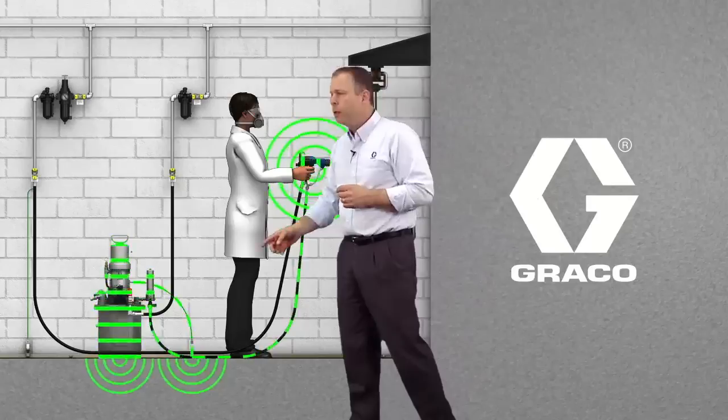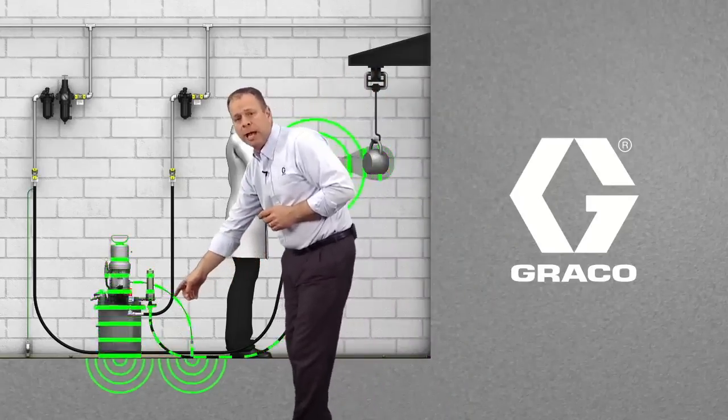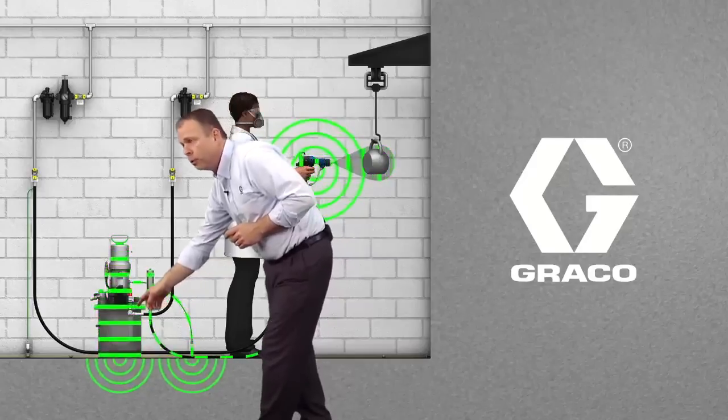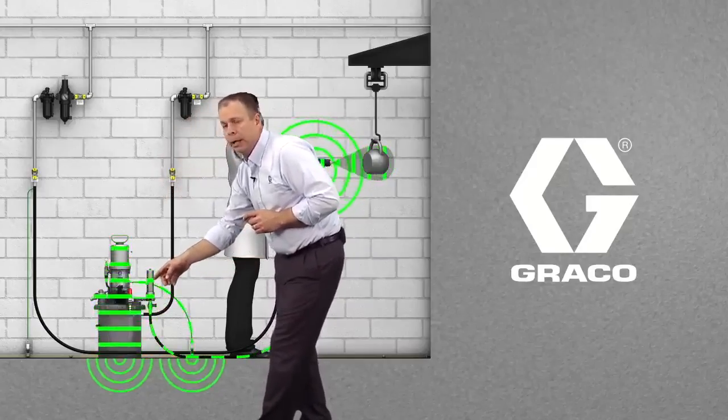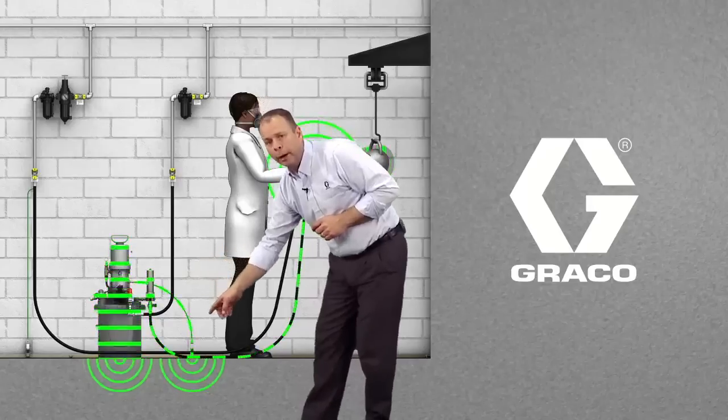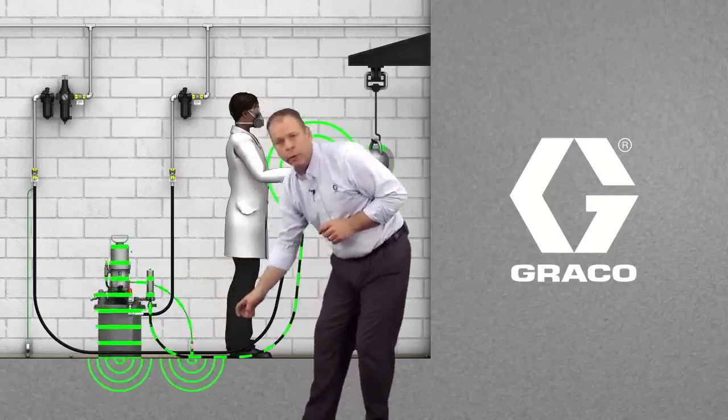There's two grounding points here. The first one, because this is a metallic pail, is through the pail itself to the surface or to the ground. The next point is going to be an actual ground wire from the pump to the true earth ground.